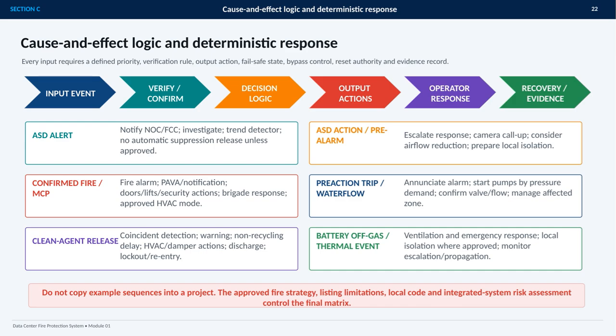An ASD alert may trigger notification and investigation, but not automatic suppression release unless approved. A pre-alarm escalates the response and prepares isolation. Confirmed fire or manual call point operation can initiate alarm notification, building system actions, brigade response, and the approved HVAC mode. Preaction or water flow events require alarm enunciation, pump response, and zone management. Clean agent release depends on coincident detection, warning, delay, discharge, and controlled reentry. Battery thermal events require ventilation, emergency response, and monitoring for escalation. These are examples only. The approved fire strategy, system listings, local code, and integrated risk assessment determine the final matrix.